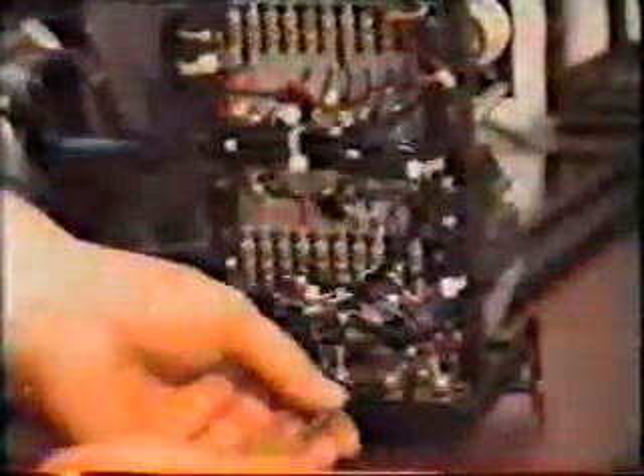All terminal connections and other screws should be tightened. Examine the wires to make sure that none are broken. The target mechanism should be checked for operation and resetting. Report any discrepancy so that claims can be made on the supplier or contractor.